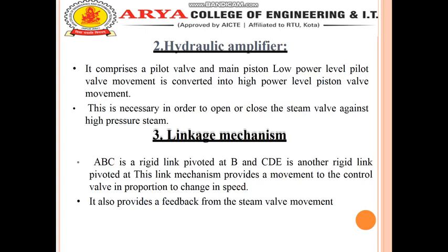The second one is the hydraulic amplifier. It comprises a pilot valve and main piston. Low power level pilot valve movement is converted into high power level piston valve movement. This is necessary in order to open or close the steam valve against high pressure steam.